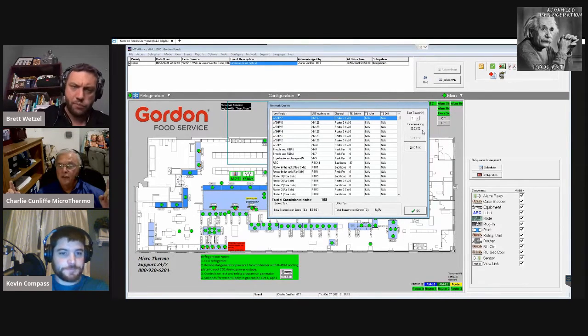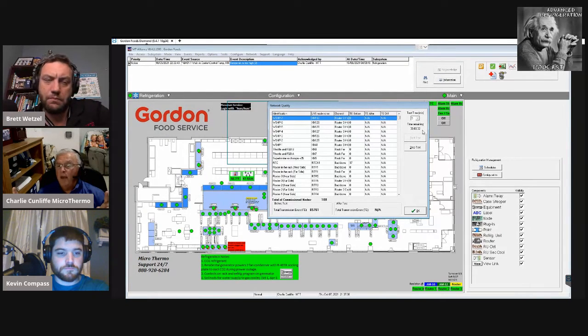You're allowed to have, as far as cable length is concerned, 1,640 feet. And within that 1,640, if they're simple nodes like an MT500, 508, 512, you can have a total of 64. We round the number down, we just say 60. If they're compound nodes like the case controller, we say 50, because they're communicating so much when they're a compound node.